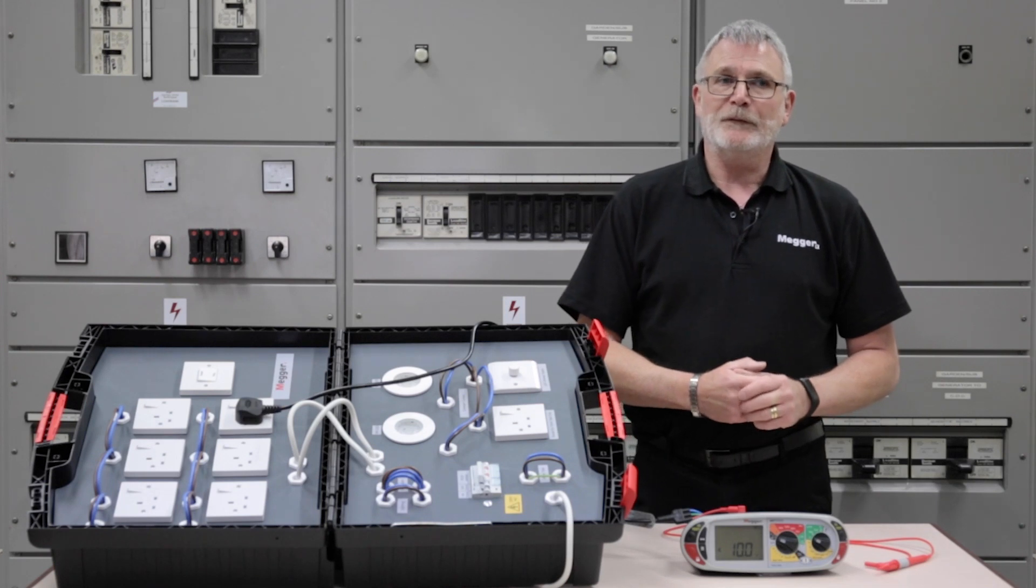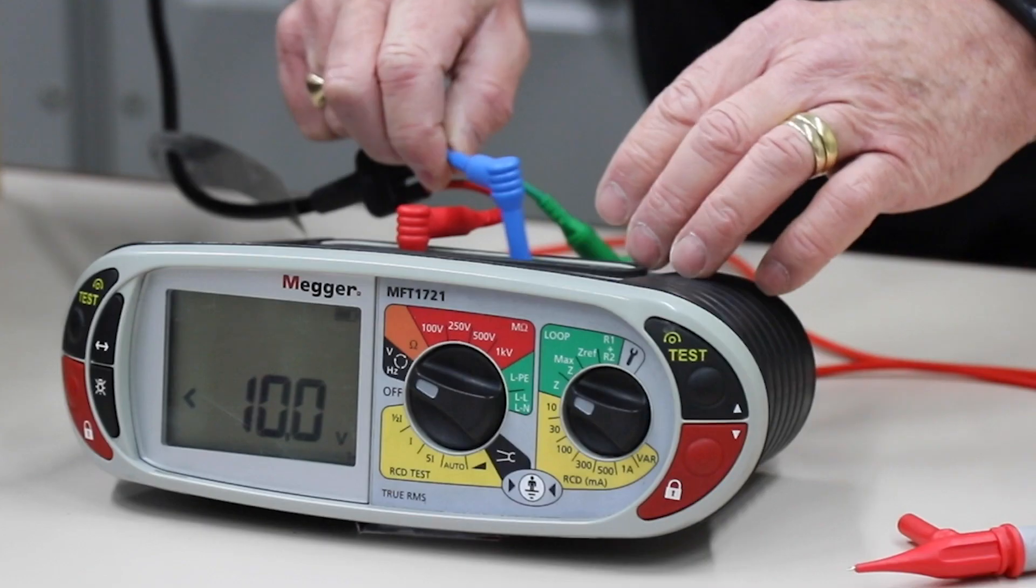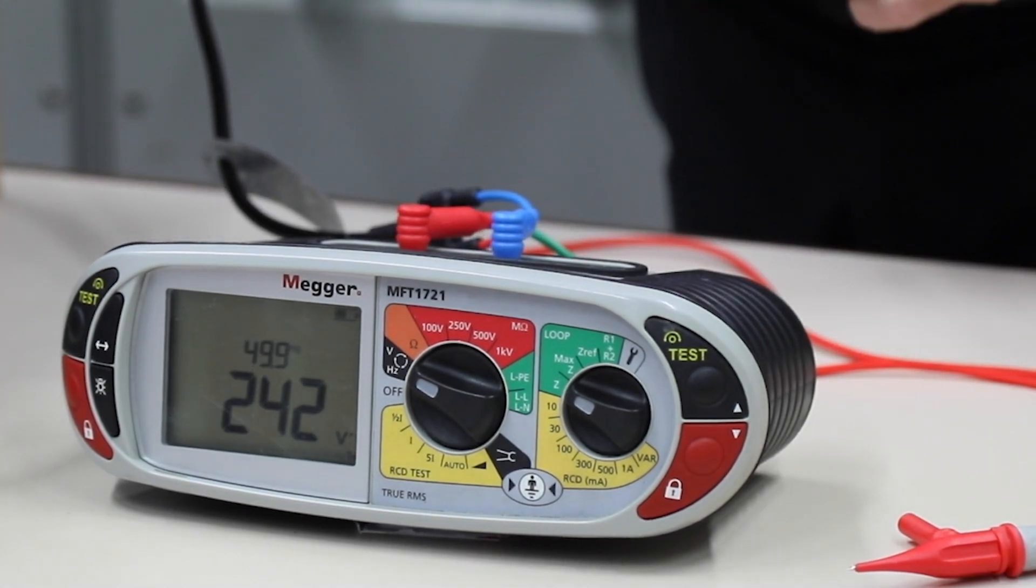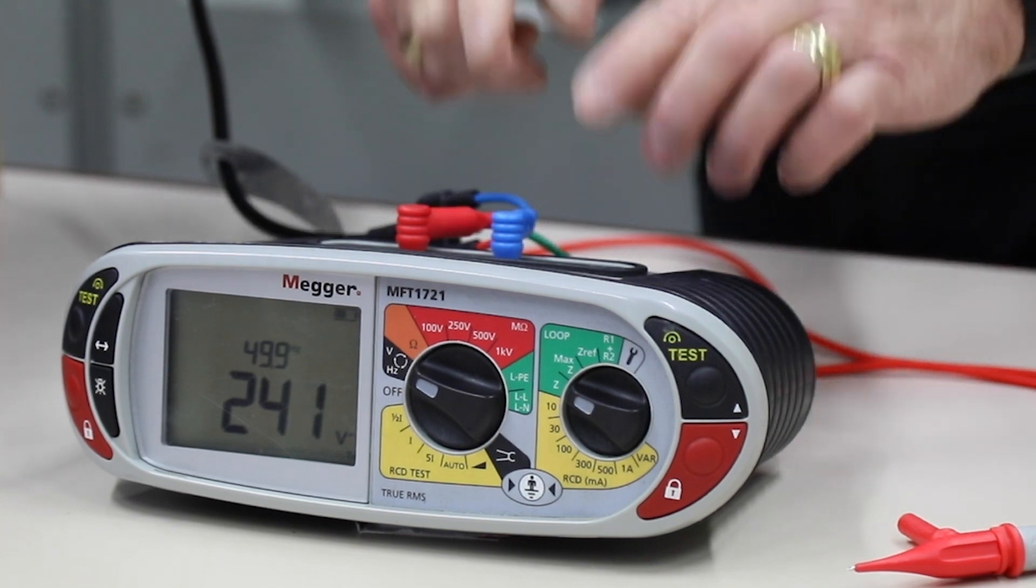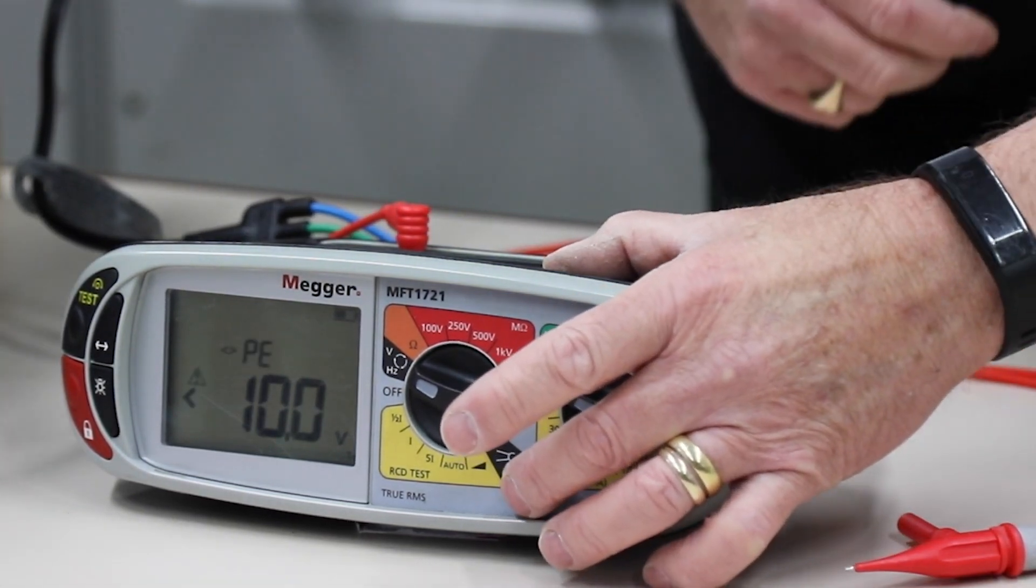That will only give you the fact that there is potential there. If you want to know what voltage is present, then go to a known earth or neutral, put the second lead in and then that will give you the voltage present. But as I say, that's potential difference. The actual tester for the touch voltage is just using potential.